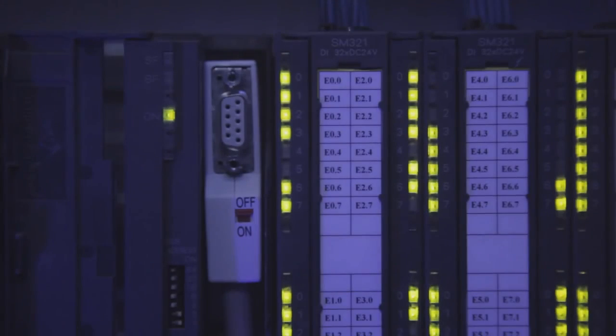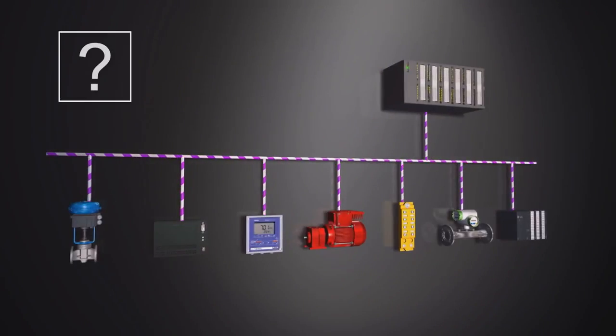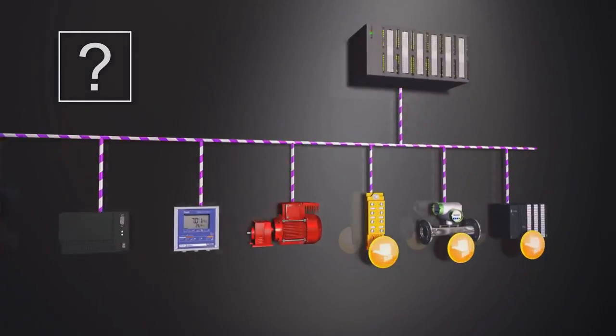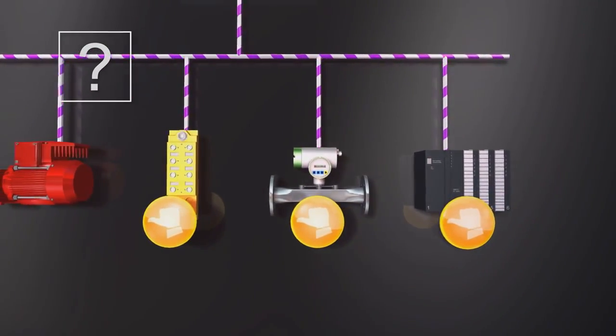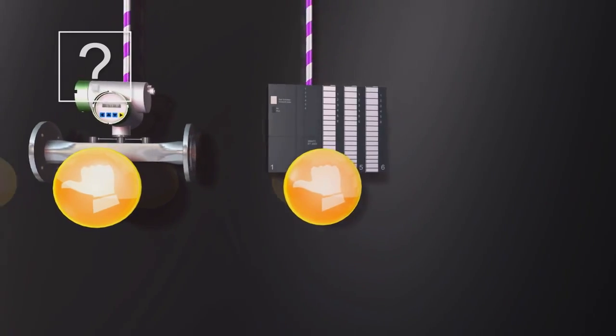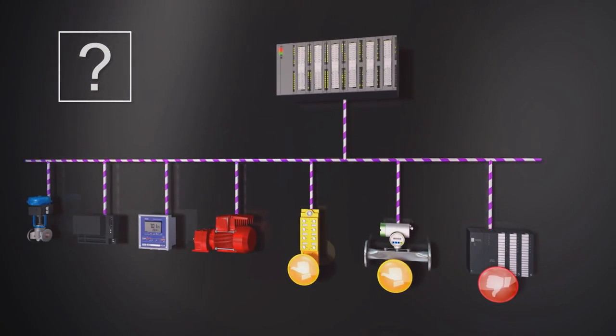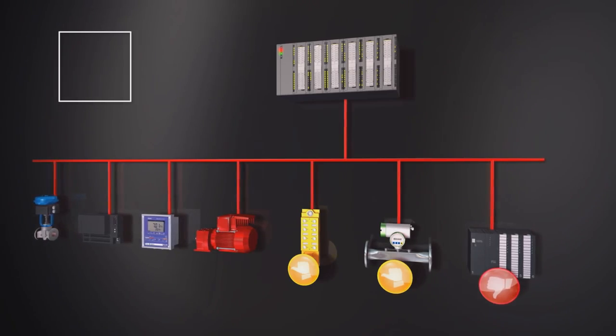After setup and commissioning, the green LEDs are by no means a proof of correct installation, let alone a guarantee of long-term operation. In fact, more than 25% of Profibus installations in the field have faults that will sooner or later lead to system downtime.